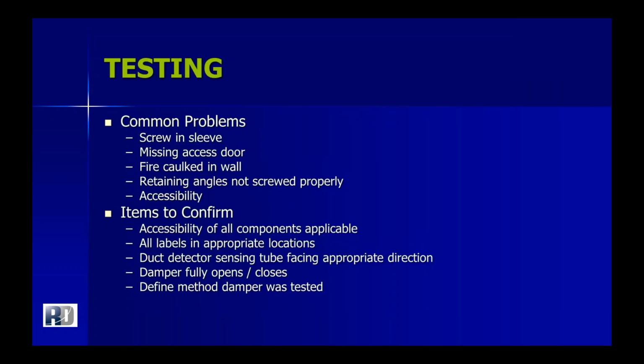So testing. Oftentimes we find common problems when we go to test a damper, like there's a screw in the sleeve. And while contractors do tend to stroke their dampers open and close when they install them, construction continues and things happen. So it's important at the end of the process to test these dampers. Many times we find missing access doors where you can't even see the damper, or the damper's fire caulked into the wall, or retaining angles aren't screwed properly, or you have an accessibility concern. So we're always looking to confirm that all applicable components are accessible.